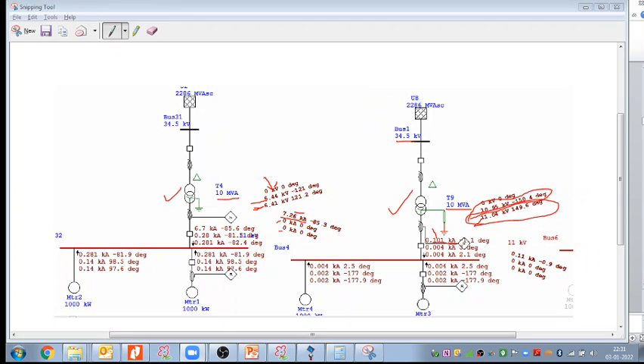Yes. Since in my extra high voltage system, my breaker uses unit protection. I will come again later on to what the meaning of unit protection is. But we can write here as a statement that in extra high voltage, we use unit protections. We use distance and differential protections for the equipment protection, and they operate instantaneously. They operate in around 40 to 60 milliseconds. So even though a very large fault current is coming, the relay will operate instantaneously and the breaker will operate within 40 to 60 milliseconds. The system will isolate very quickly, and that is not going to damage any equipment.